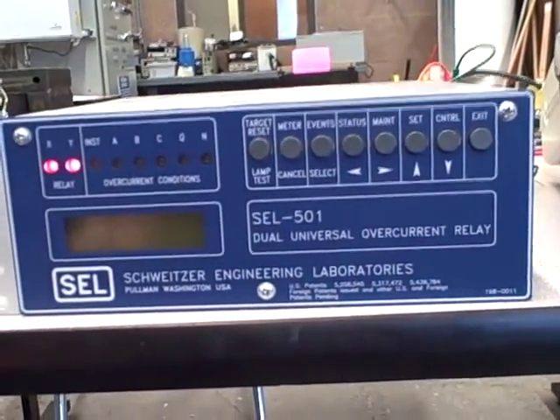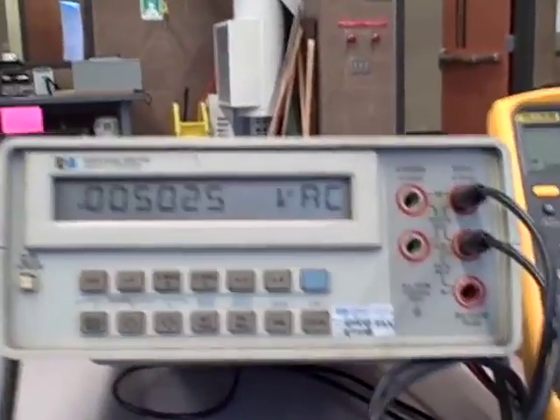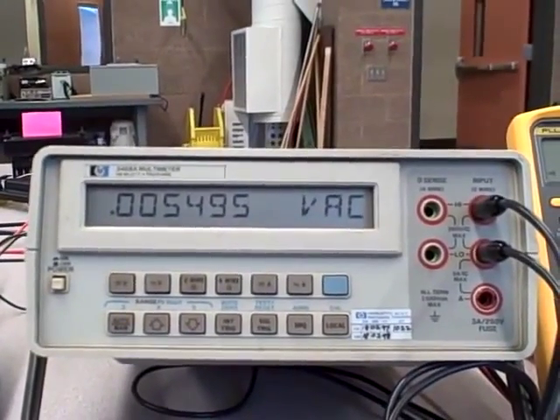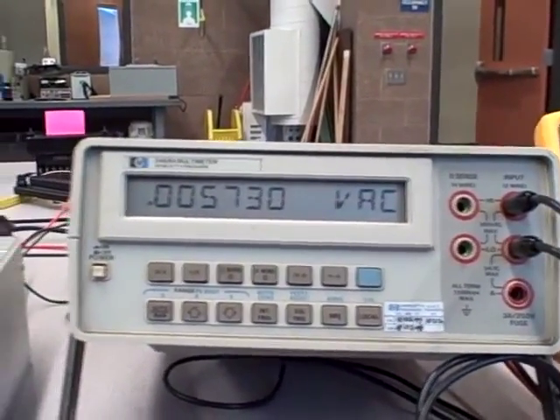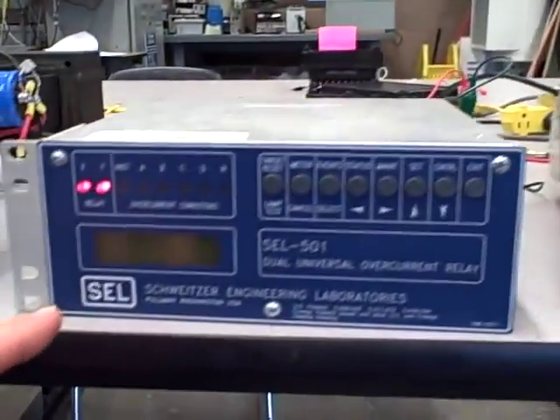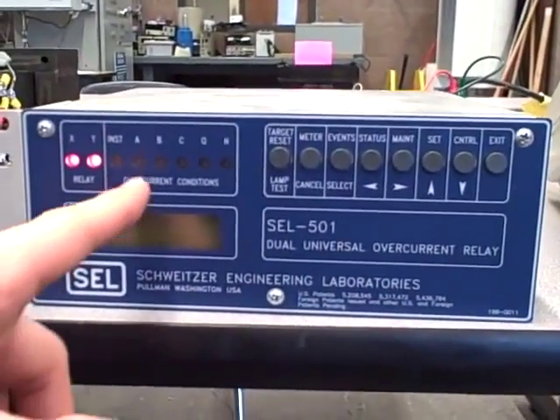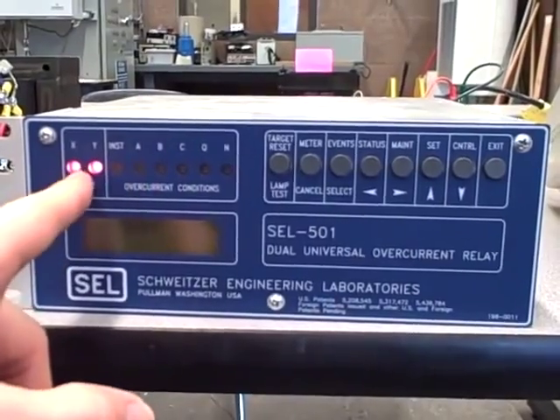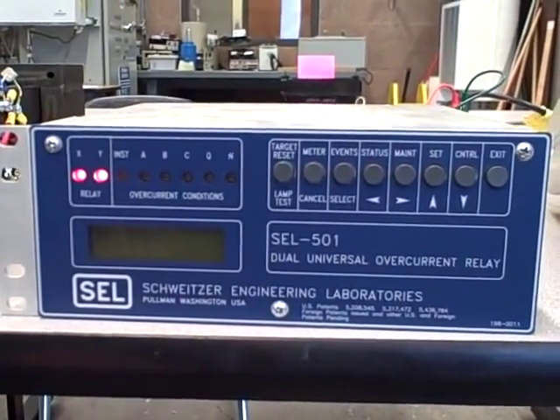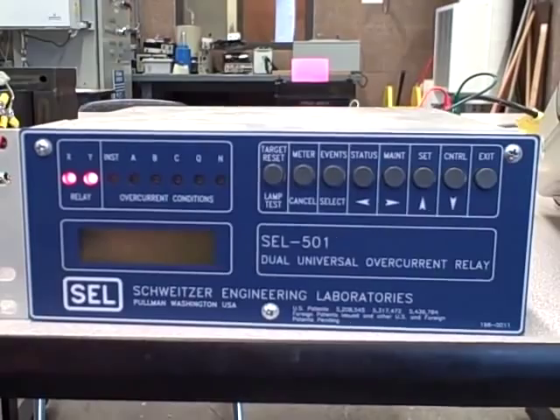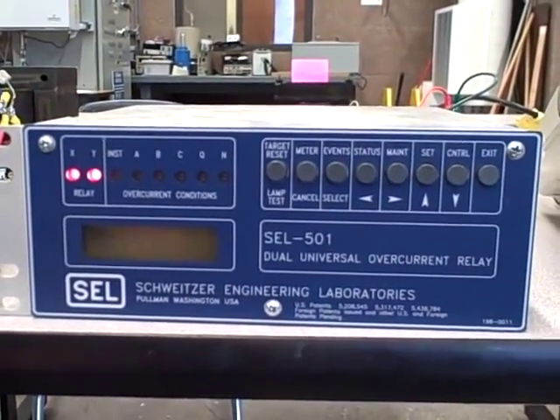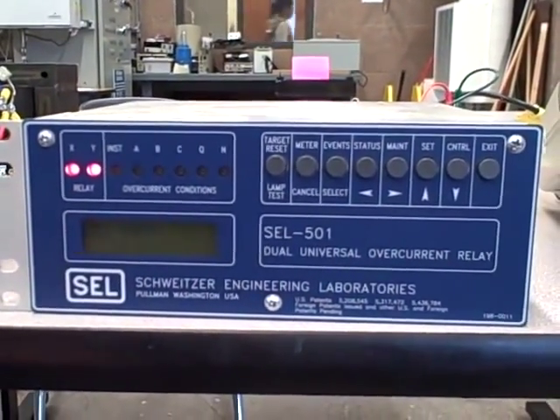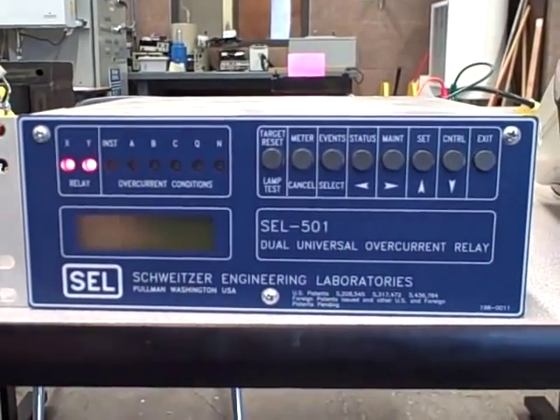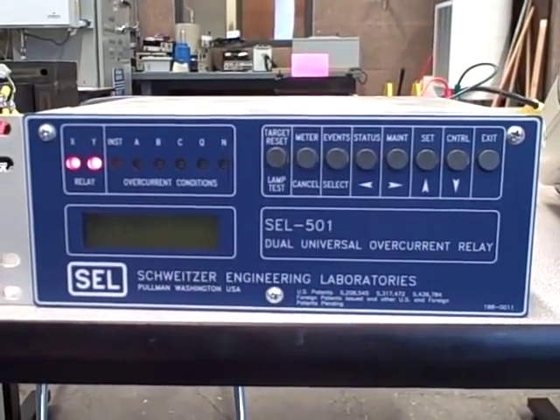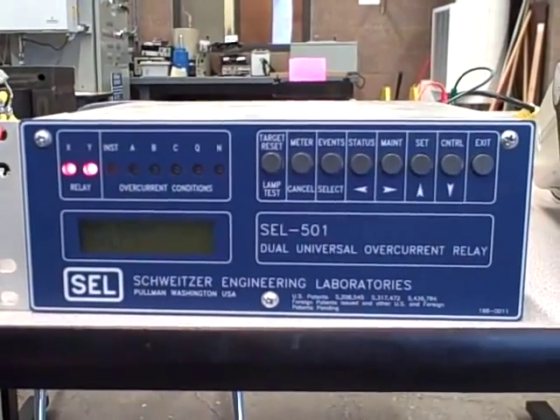What I'm going to do is hasten this a little bit. I'm going to increase my current so a little bit more than 5 amps. And when we do this, we're going to see fairly soon, we'll get an actual trip on the relay. So we're going to sit here and watch the front panel. We expect to see an overcurrent condition on phase A for relay X. We just give it enough time. Again, we're beyond the line current value that we established for a pickup. We're just waiting for the overcurrent curve to reach its set time, and then it's going to actually trip the relay.